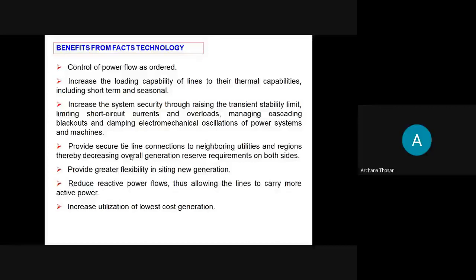So the line should have the capacity to withstand that temperature. Then the dielectric means, from an insulation point of view, whenever high voltage is passing, it should withstand that. And the stability will be in terms of transient stability, dynamic stability, steady state stability, frequency collapse, voltage collapse, and some resonance issues. So these are the things which govern the loading capability of a line.